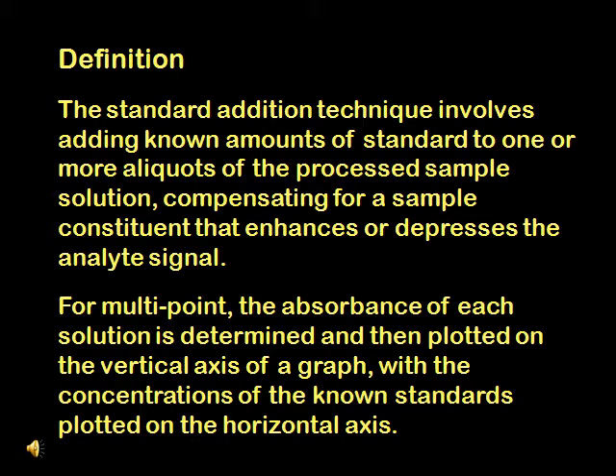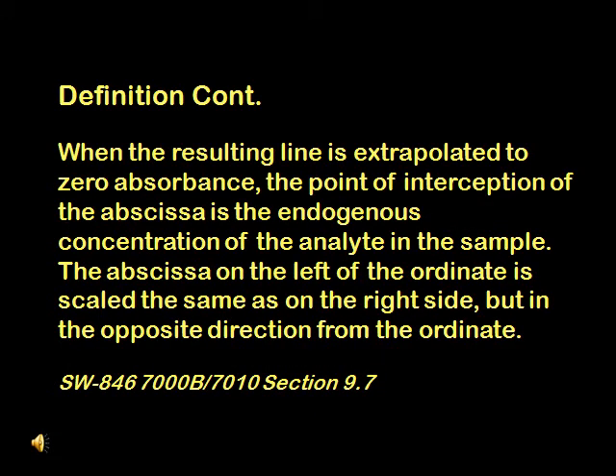For multipoint, the absorbance of each solution is determined and then plotted on the vertical axis of a graph, with the concentrations of the known standards plotted on the horizontal axis. When the resulting line is extrapolated to zero absorbance, the point of interception of the abscissa — which is the horizontal coordinate of a point in the plane obtained by measuring parallel to the x-axis — is the endogenous concentration of the analyte in the sample.